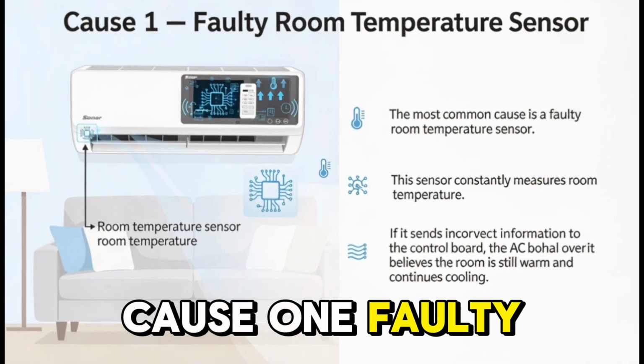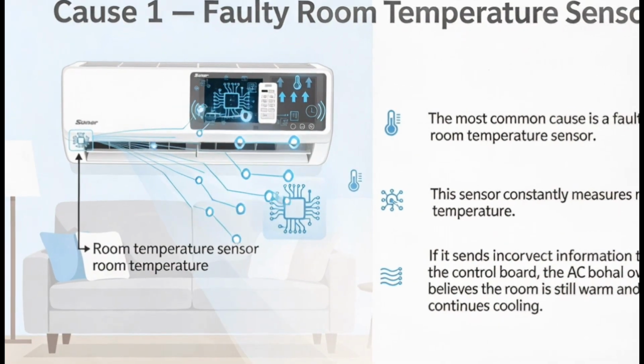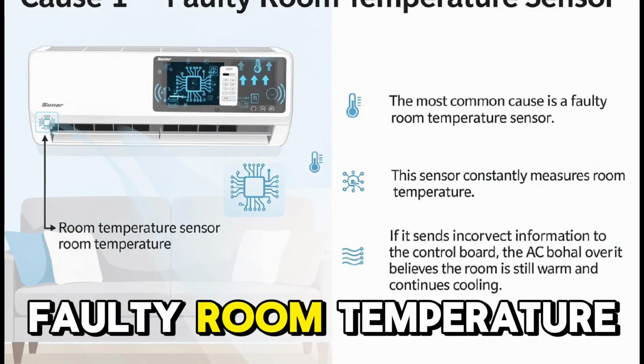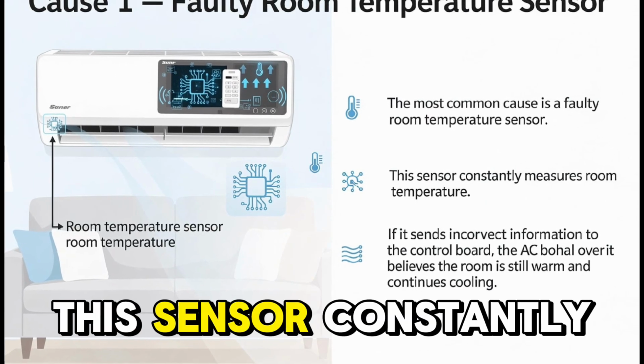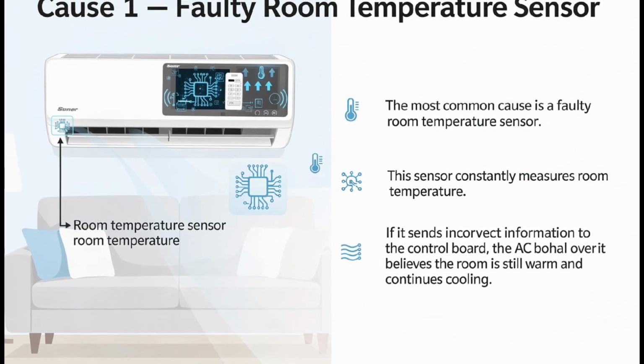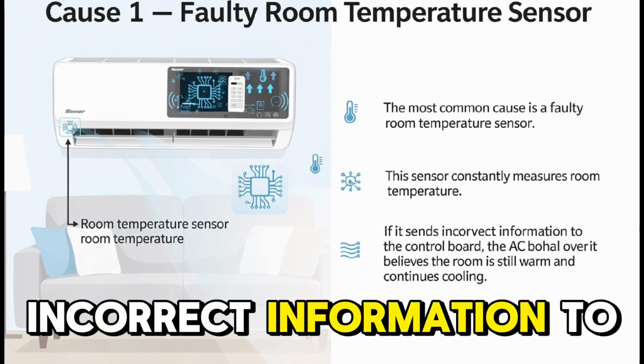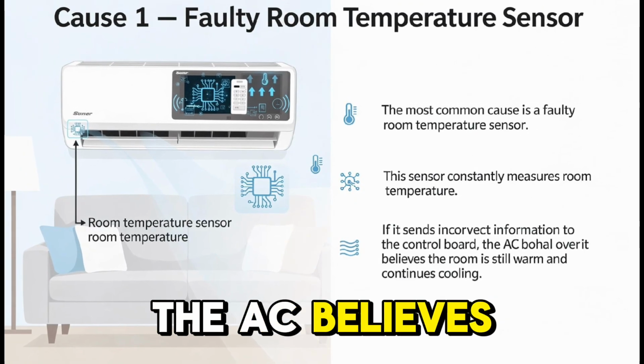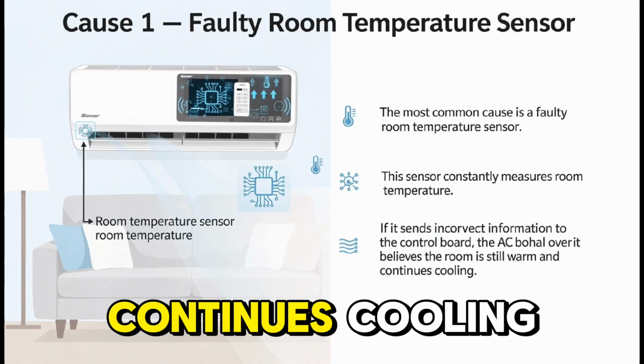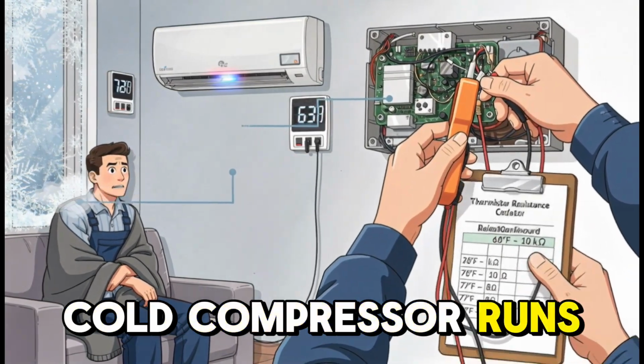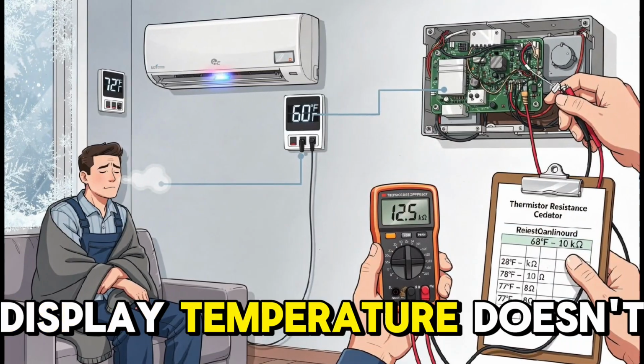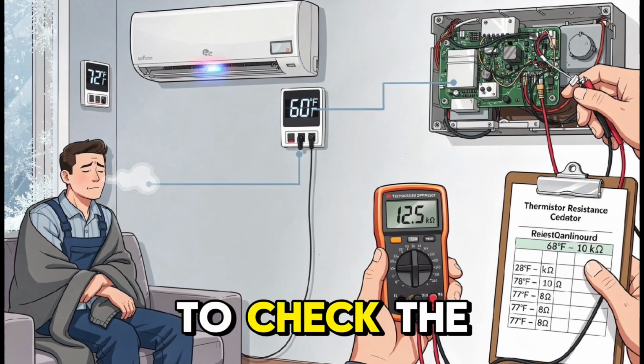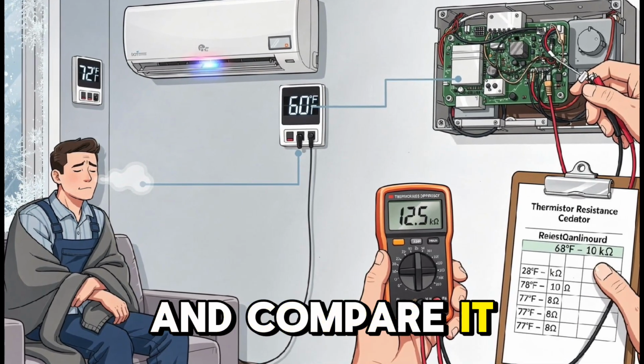Cause 1. Faulty room temperature sensor. The most common cause is a faulty room temperature sensor. This sensor constantly measures room temperature. If it sends incorrect information to the control board, the AC believes the room is still warm and continues cooling. Room becomes too cold. Compressor runs continuously. Display temperature doesn't match the actual room temperature. Use a multimeter to check the thermistor resistance and compare it with the manufacturer's resistance chart.